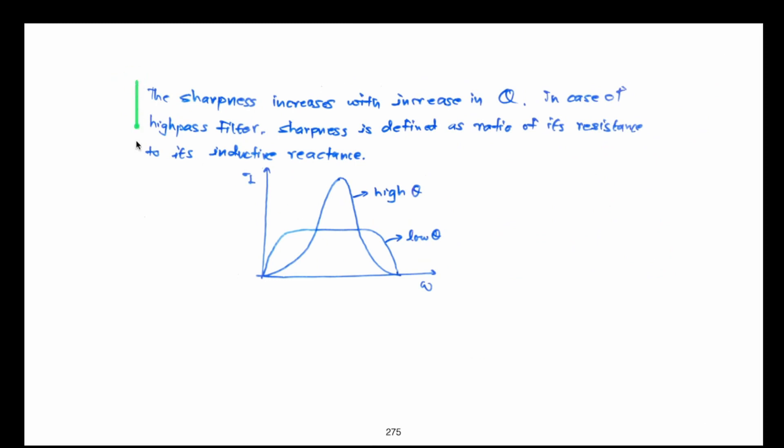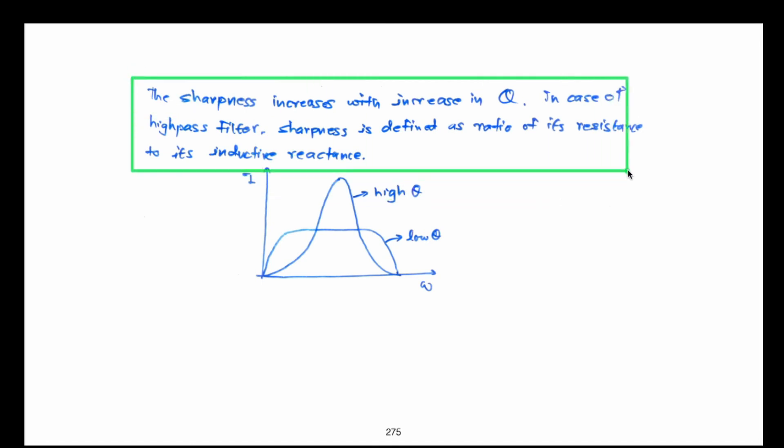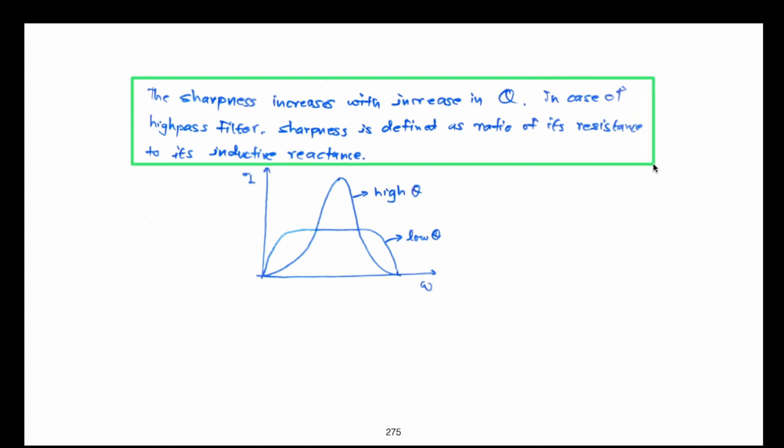The sharpness of tuning increases with the increase in the value of Q factor — the larger the Q factor, the greater the selectivity. For high-pass filters, the Q factor is defined differently: it is the ratio of resistance to inductive reactance, exactly the reverse of a single-tuned filter, because high-pass filters pass all frequencies above a certain cutoff frequency.